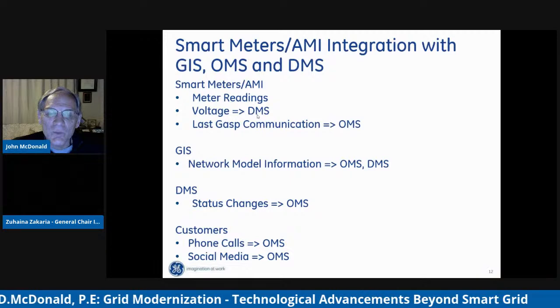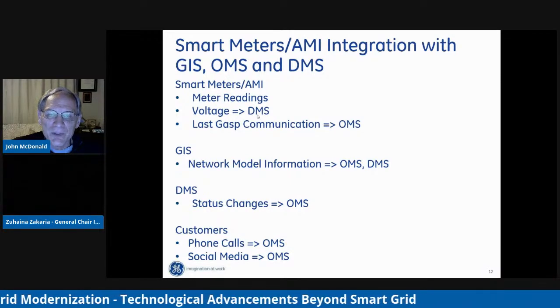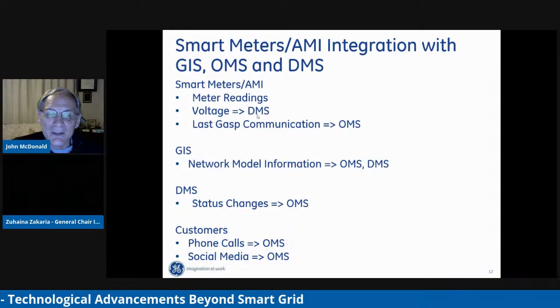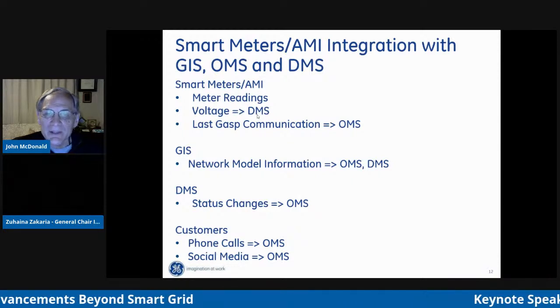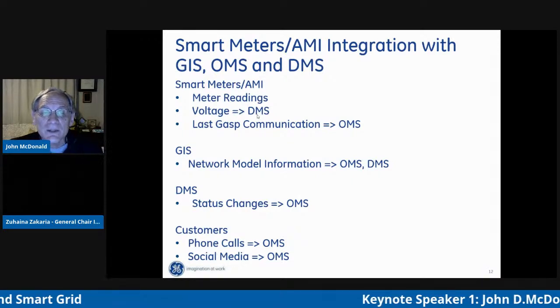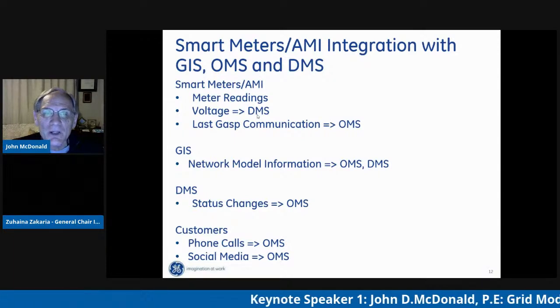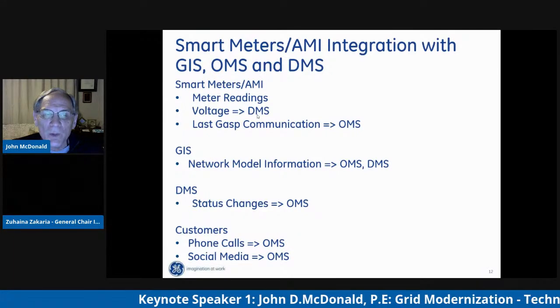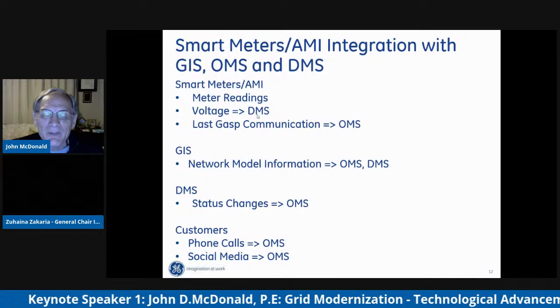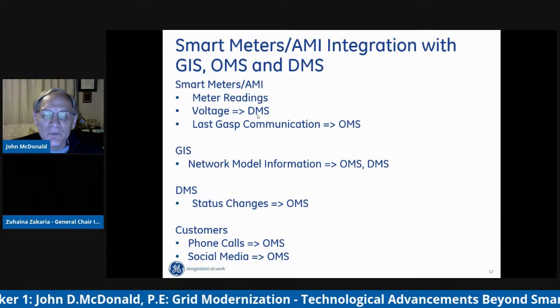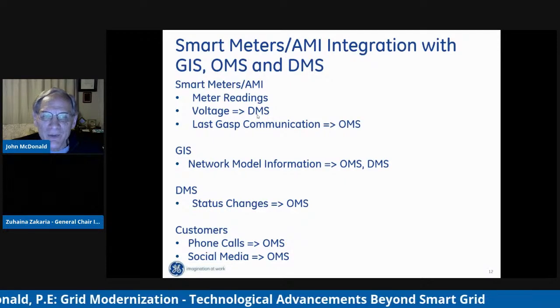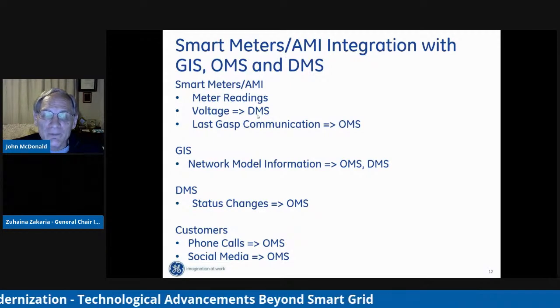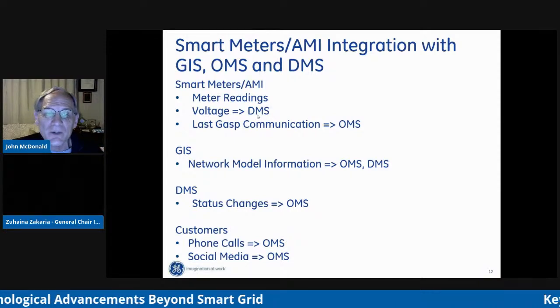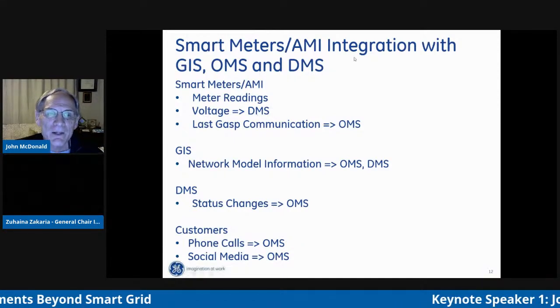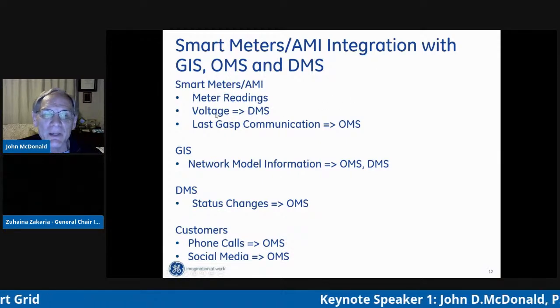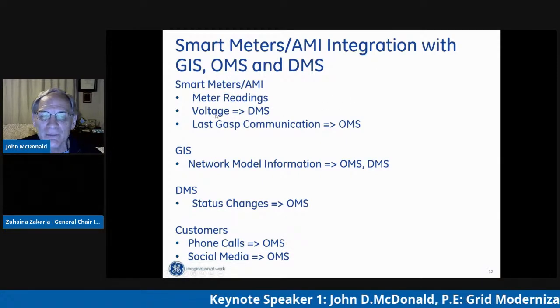In the United States, we have 120 plus or minus 5%. It's an ANSI standard, American National Standards Institute, C84.1, that says the voltage at the customer premise must be 120 plus or minus 5%. So we don't want to get near 114 volts, which is 120 minus 5%. We want to know what that voltage is, particularly on long feeders with more voltage drop, so we can ping smart meters at the ends of those feeders to find the voltage.